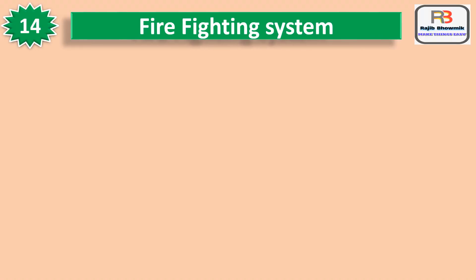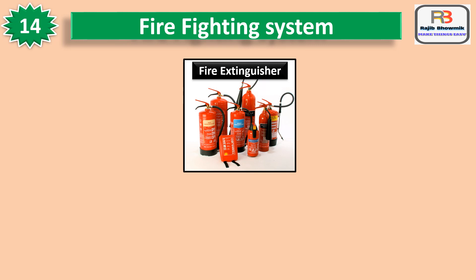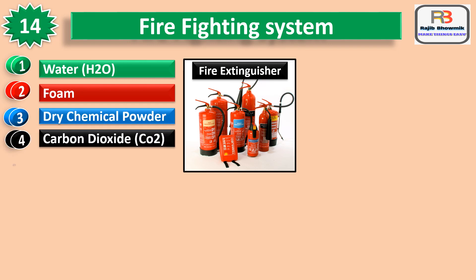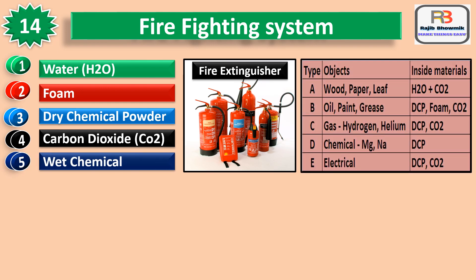Number fourteen is Fire Fighting System. There are five types of materials used in fire extinguishers: water, foam, dry chemical powder (DCP), carbon dioxide (CO2), and wet chemical. There are five types of fire: A-type for wood, paper, leaf — using H2O and CO2; B-type for oil, paint, grease — using DCP, foam, CO2; C-type for gas such as hydrogen and helium — using DCP and CO2; D-type for chemicals such as magnesium and sodium — using DCP; and E-type for electrical — using DCP and CO2.